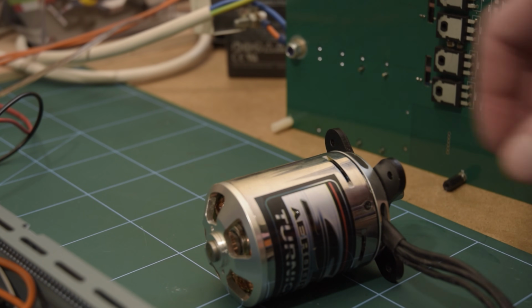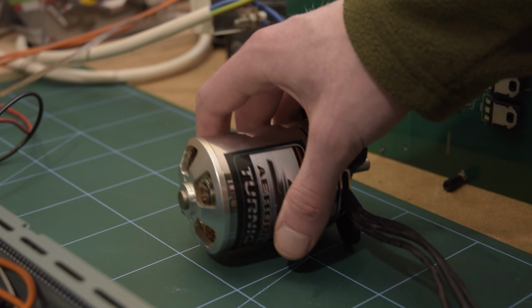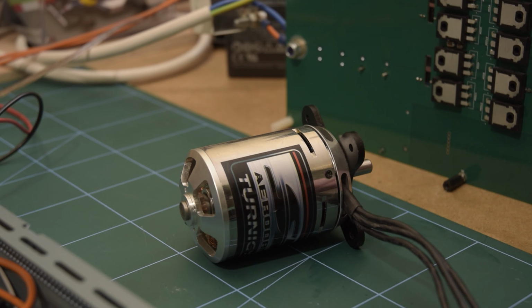That might make synchronous motors seem useless, but if you have feedback coming back to the inverter, you can make this the best type of motor. For that you need rotor position sensing - in high-end motors you might have a resolver, a rotary encoder, Hall effect sensors, or you can sense the back EMF on the motor, which is how low-end motors like this are intended to be operated.